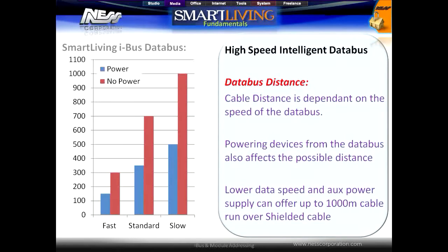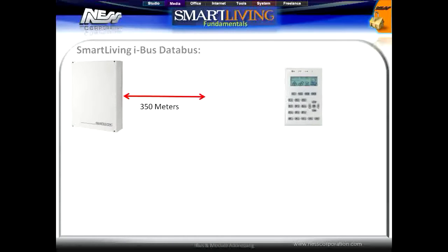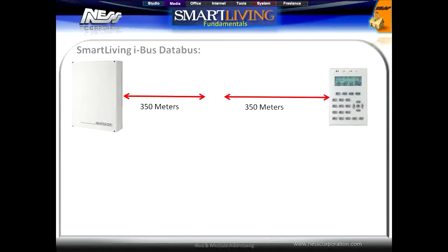Data bus distance is dependent on both speed and how many devices are being powered from the system. To increase data bus distance, simply decrease the speed of the data bus or power devices from an auxiliary power supply. In cases where we need to increase the data bus distance further, we can install a data bus isolator, which will increase distance, isolate both sides of the data bus, and regenerate and boost power for long cable distances.